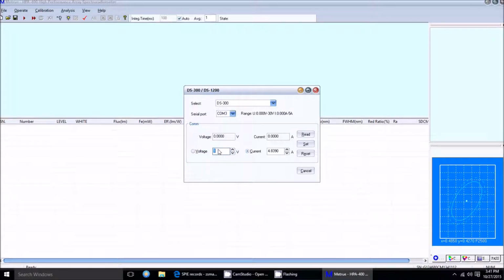However, I have to set it slightly higher, or it won't turn on. Because I've set it here, it keeps the current the same always, and then the voltage will be whatever the voltage ends up being, which should be very close to the reference voltage, which for me is 20. So I'm going to actually put it to, let's say, 24.89. It's 4 volts higher. So if I set it, it should be on. I'm going to check real quick and open the sphere.